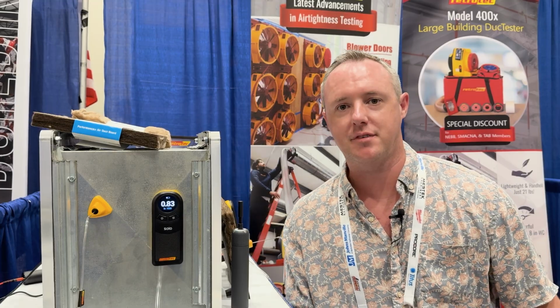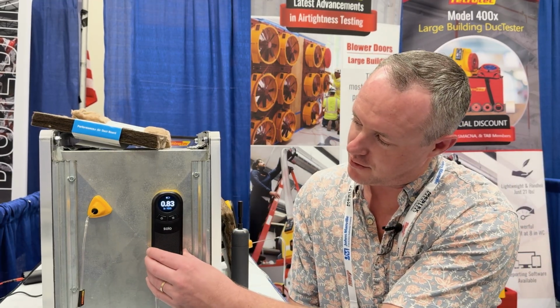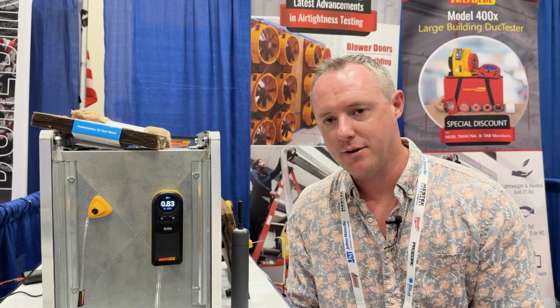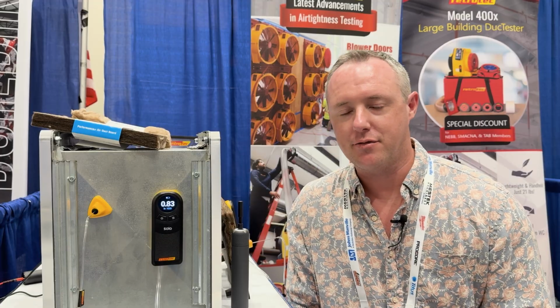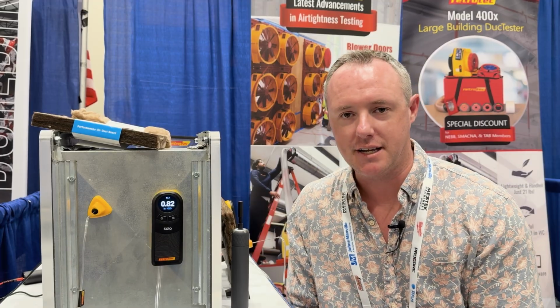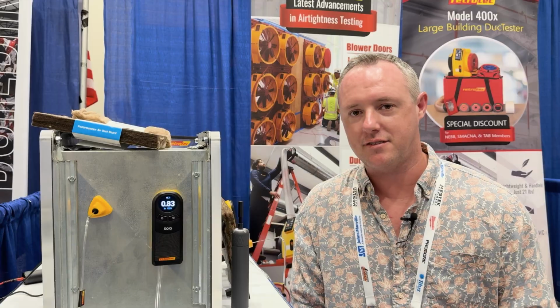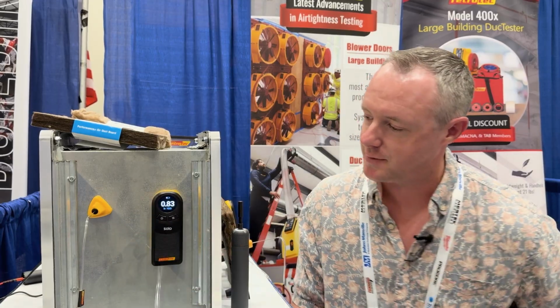I want to take this opportunity to show you how you can use our multi-probe to read static pressures in duct systems. This is our solo single channel manometer, a high resolution manometer that can read pressures down to a fraction of a pascal, but you can also read it in inches of water. It's a great device to read static pressures with the multi-probe attached to it.